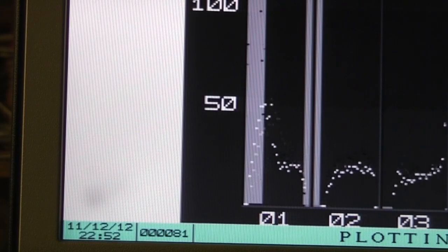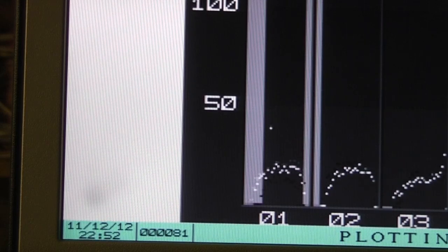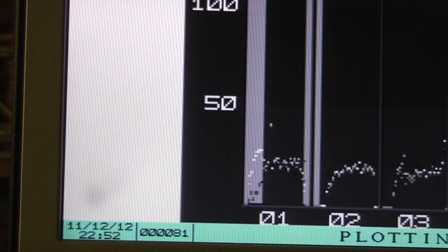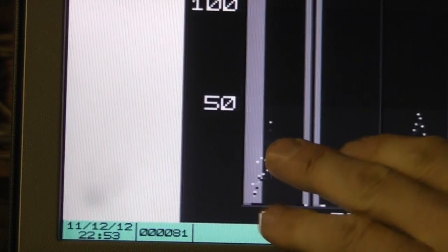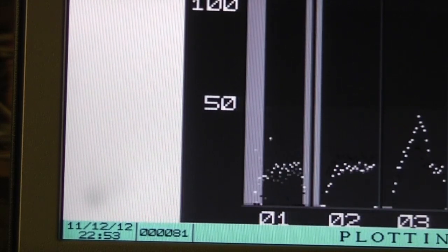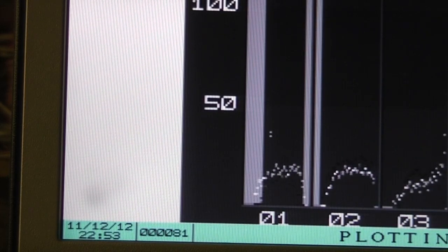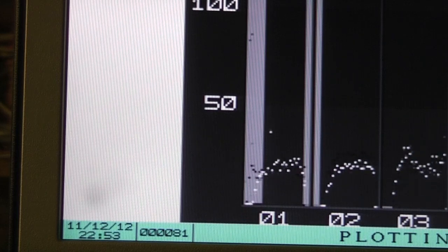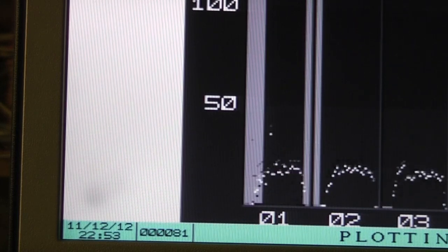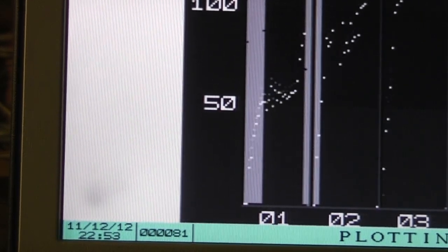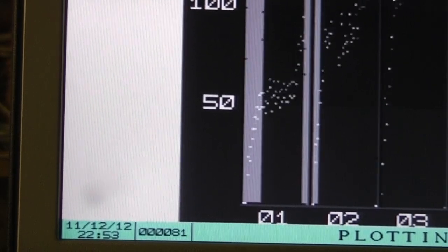It's a little bit hard to get rid of all the light signals without working in total darkness. What I'm going to do is take a look at this one little signal here that's higher than all the others. I'm going to try swapping the two diode arrays from this bottom one to the one above it, just to see if that spot moves or stays in the same place, and that'll tell us whether it's associated with an individual diode or something else.